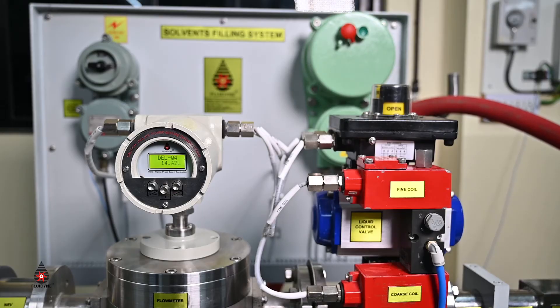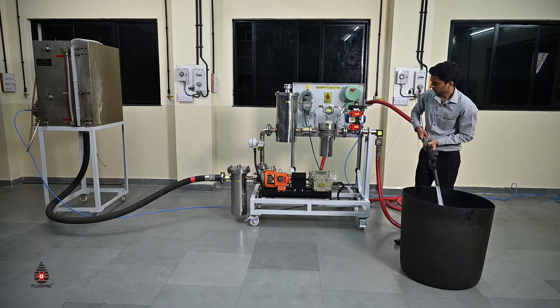Connections such as this nozzle or flange ends to piping are possible. The air separator and back pressure valve ensure no ingress of air due to emptying compartments or vertical lines that drain due to gravity. This enables the PD meter to achieve best accuracy.